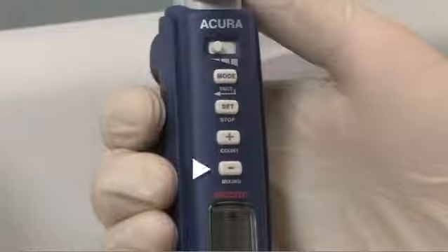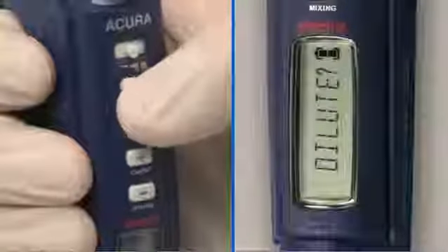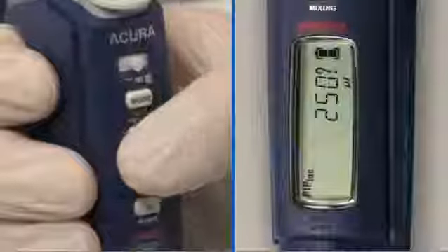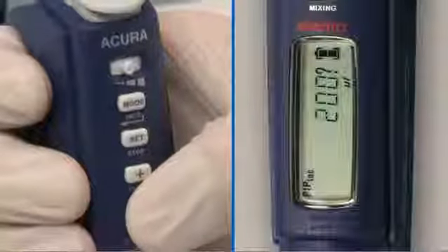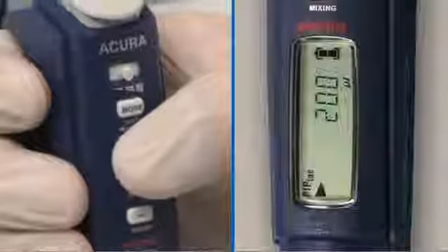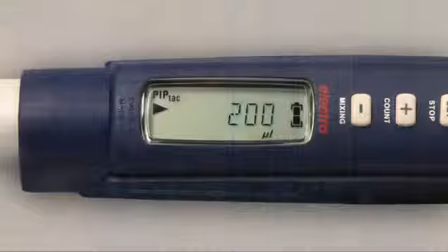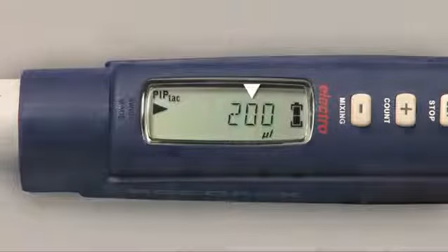Mixing creates a vortex by an up and down liquid flow in the tip or vial. It's activated by a simple touch of the key when pipetting is completed. Releasing the Mix key stops the mixing action. Tactile mode enables a precise monitoring of the plunger movement by a simple touch of the Start button. It is extremely efficient for titration and gel loading. Press mode several times until the display shows Tactile. Press Set to validate. Press the plus/minus keys to display the maximum aspirated volume. Press Set to validate. The display shows the selected mode and volume.